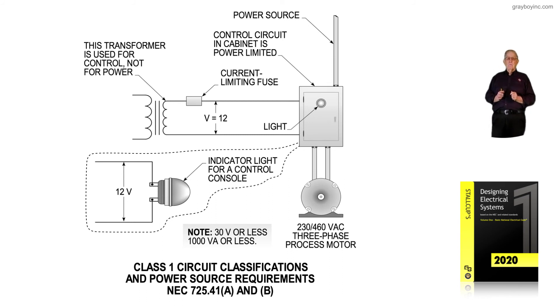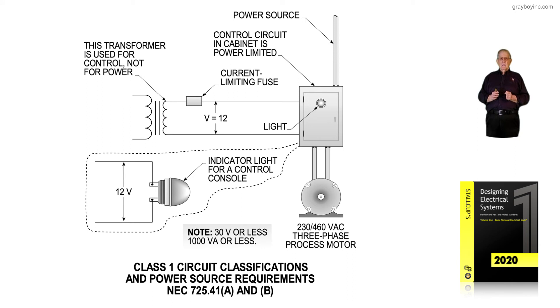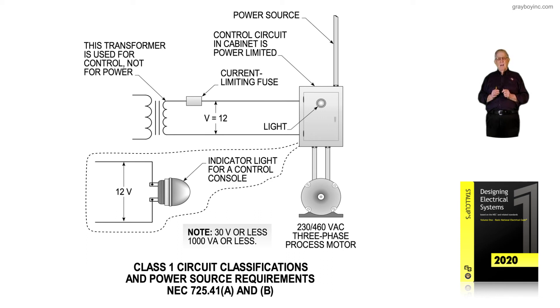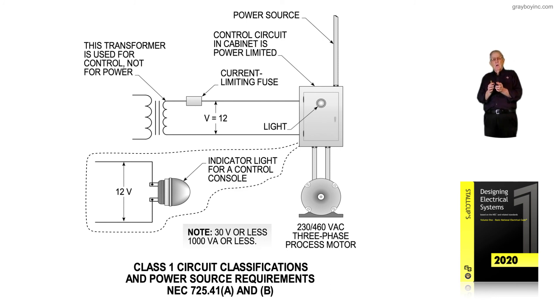You have to evaluate them to see if they're a shock hazard or an arc hazard. That transformer could be mounted remotely in an enclosure, or it could be directly in the enclosure. If it's a non-power-limited circuit and you have 460 volts coming into that enclosure, you could tap off L1, L2, or L3 lines to supply voltage to the contactor. NEC Table 430.72 regulates that installation whether conductors are inside the enclosure or mounted remotely with a pressure switch, flow switch, or any other switching device.